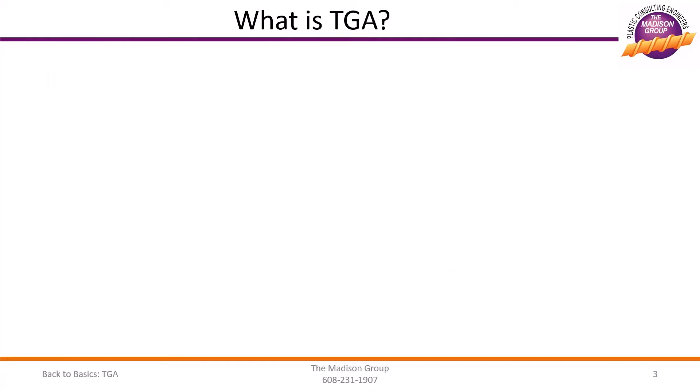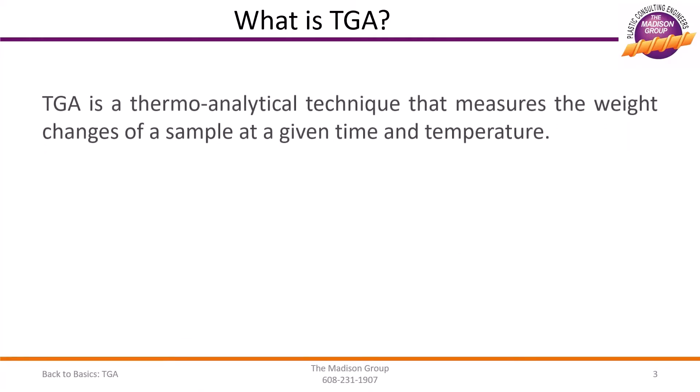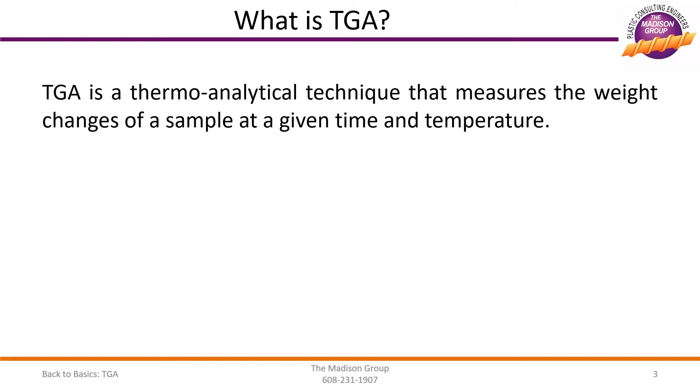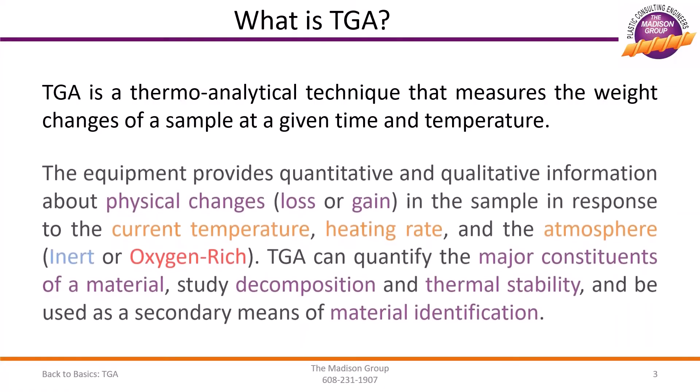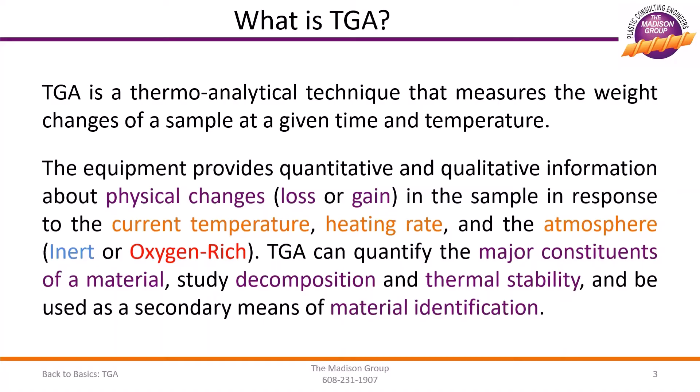You may be wondering, what is thermogravimetric analysis? TGA is a thermoanalytical technique that measures the weight changes of a sample at a given time and temperature. The equipment provides quantitative and qualitative information about physical changes, whether weight loss or gain, in the sample in response to the current temperature, heating rate, and the atmosphere, whether it's inert or oxygen-rich. TGA can quantify the major constituents of a material, study decomposition and thermal stability, and be used as a secondary means of material identification.